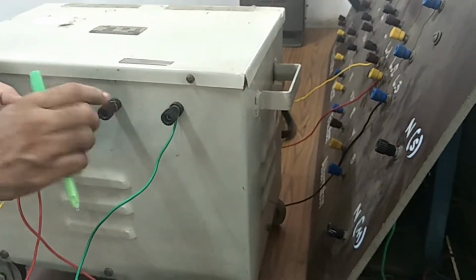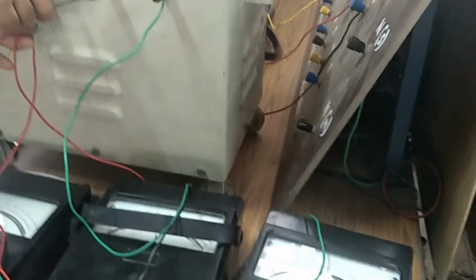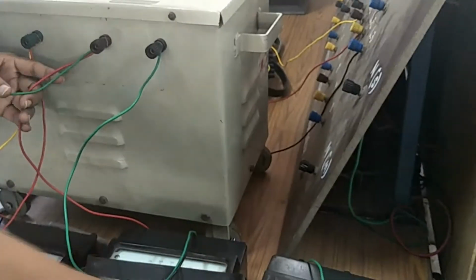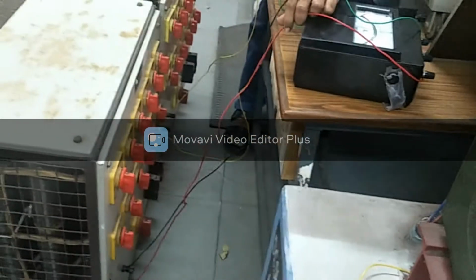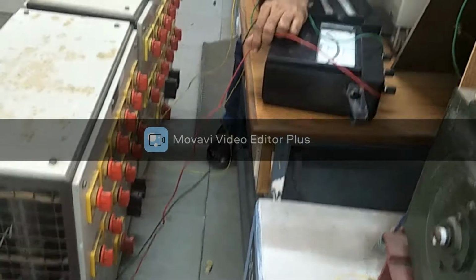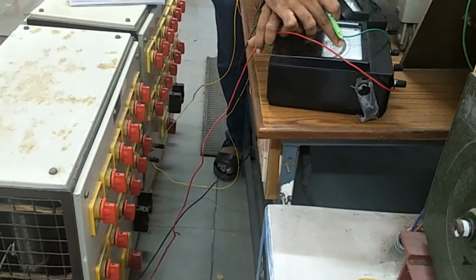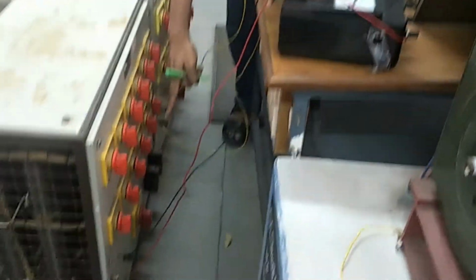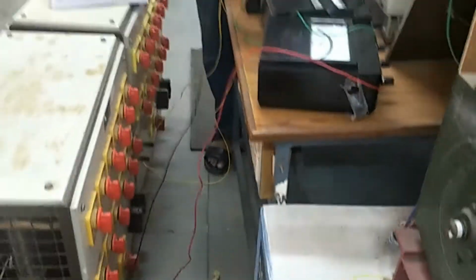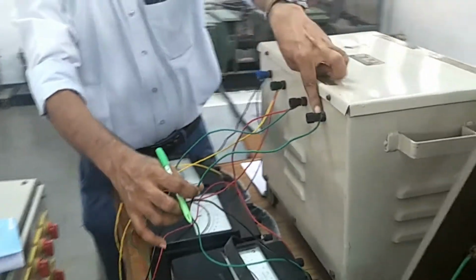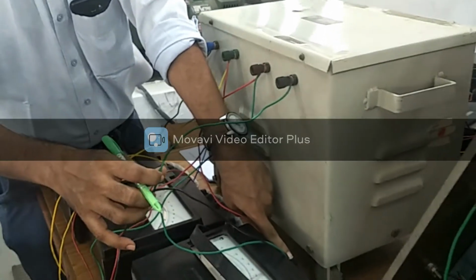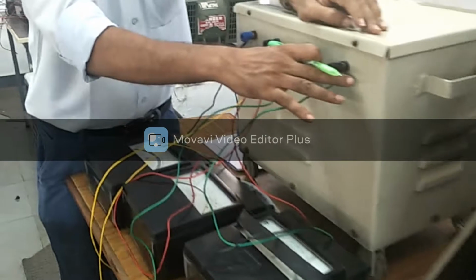Voltmeter common and ammeter common are connected to the phase. The other end of the ammeter is connected to the load. These are the two loads: the single phase load of the teaser transformer, and similarly the single phase load of the main transformer. The other end of the ammeter is connected to the 0 terminal of the load, and the other load terminal is connected to the neutral. The voltmeter's second terminal is also connected to the neutral. So this is the secondary side connections of the teaser transformer.